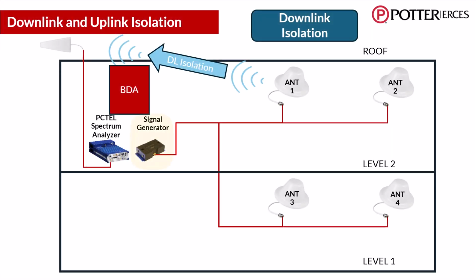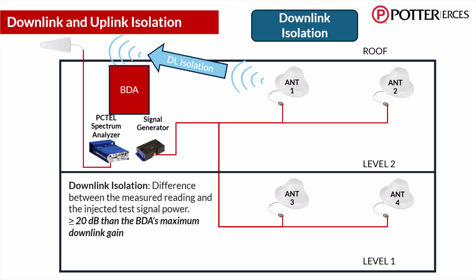The use of a signal generator and spectrum analyzer is required to conduct an isolation test. The spectrum analyzer will be connected to the end of the donor antenna cable to measure the effect the internal antennas have on the donor antenna signal. Inject 0 dBm of signal via a signal generator into the distributed antenna system and observe the difference on the spectrum analyzer. The difference between the measured reading and the injected test signal power is the downlink isolation. This should be 20 decibels or greater than the BDA's maximum downlink gain.